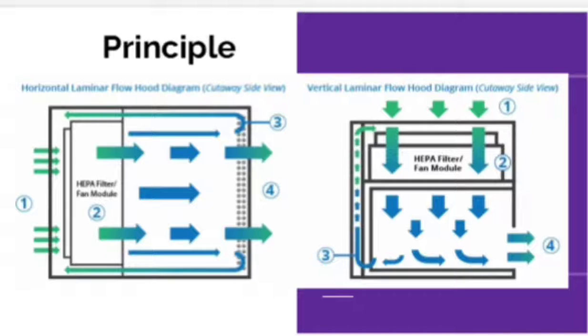Now, principle of the laminar airflow bench. The principle of the laminar airflow cabinet is based on the continuous flow of air through the cabinet. The device works by the use of inward flow of air through one or more HEPA filters to create a particulate-free environment. The air is taken through a filtration system and then exhausted across the work surface as a part of the laminar flow of the air.